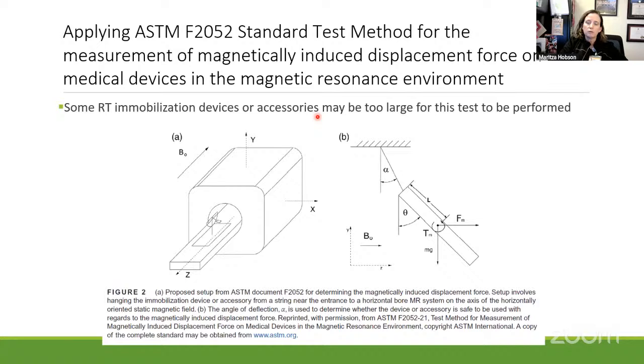So when you're applying ASTM 2052, the test for measurement of the magnetically induced displacement force, you're performing it outside of the bore, as shown by this diagram here, with a device suspended by a string. Obviously, a lot of our immobilization devices and accessories are way too large to suspend by a string, like the back locks or wing boards. It's just unrealistic.